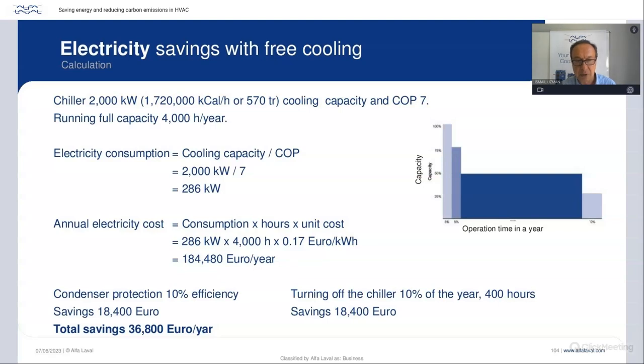So what is the cost of running the chiller? Of course, we need to take into account this 4,000 hours a year and the cost of electricity. I've taken 0.17 because at the last information, I think in Spain, it was 0.17 euro. So running this chiller 4,000 hours a year is 180,000 euro. Now, the savings with condenser protection is about 10%. The savings with turning the chiller off, say 400 hours a year, is again about 18,000. So totally 36,000 euro savings per year with this application, which is a fantastic amount of money. And the payback period is well under 1 to 2 years.